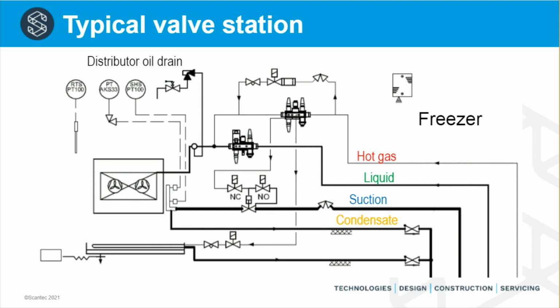The reason for that is to be able to warm up the condensate tray before hot gas is injected into the evaporator coil. These evaporators defrost rather quickly, and if the condensate tray is not warm by the time the condensate starts to hit the tray, there's a risk that it might refreeze. I haven't shown you the way the condensate is returned, but it is returned via a high pressure float valve directly back to the intercooler, not the low temperature accumulator, but the intercooler.